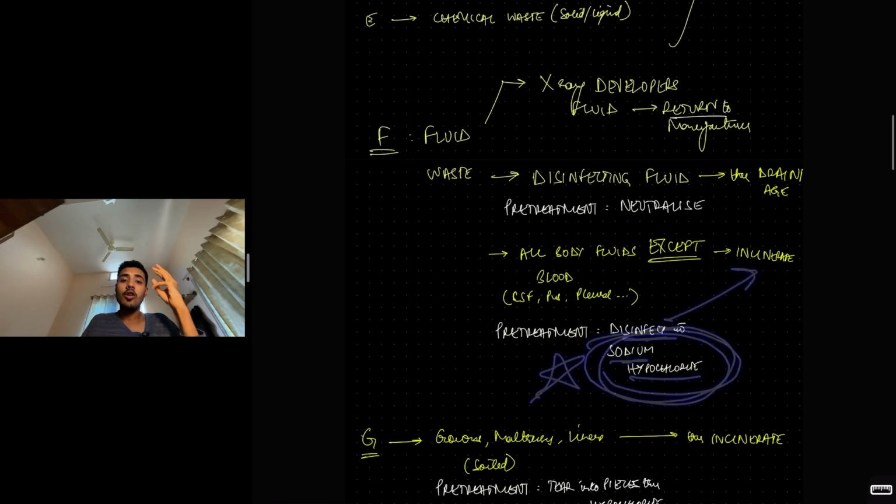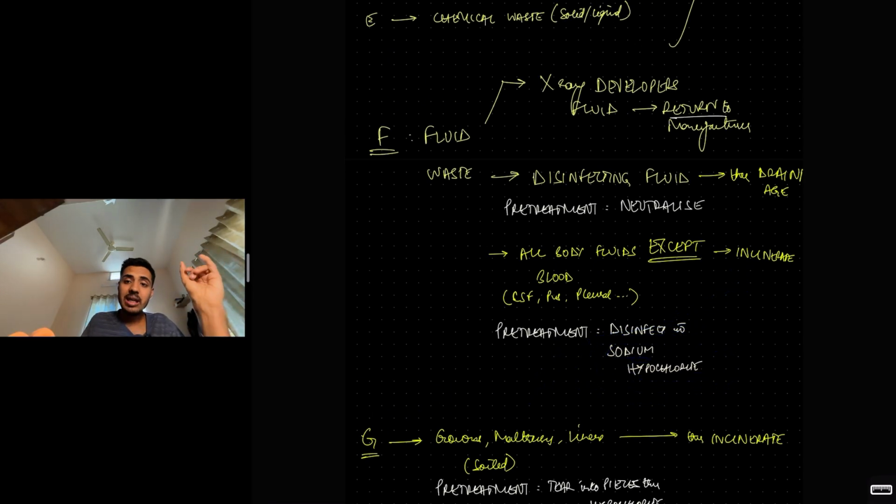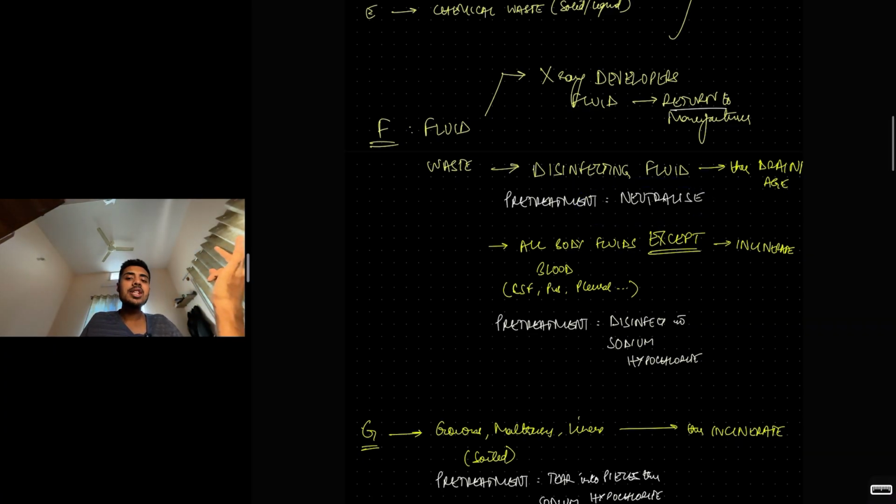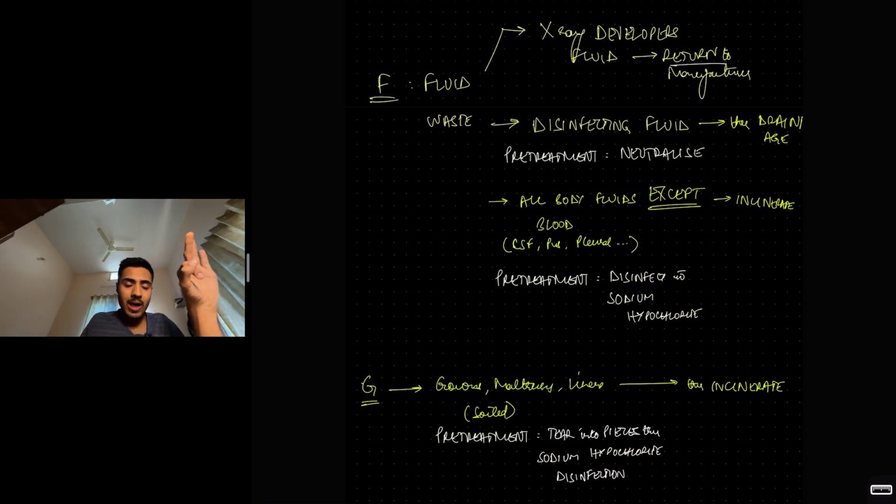So F for fluid, it requires pre-treatment. X-ray developer fluid, return to the manufacturer. Disinfecting fluid, neutralize, then put it in the drainage. And all body fluids except for blood, disinfect with sodium hypochlorite and then incinerate.